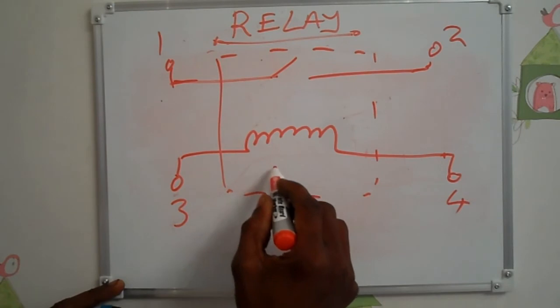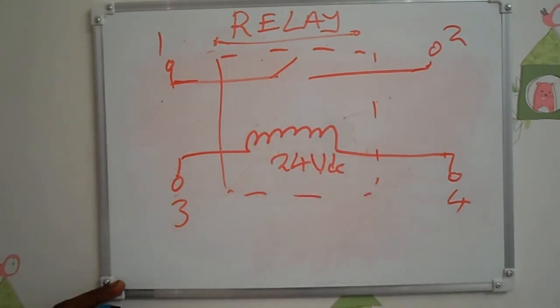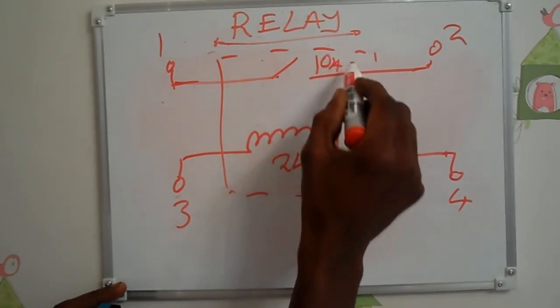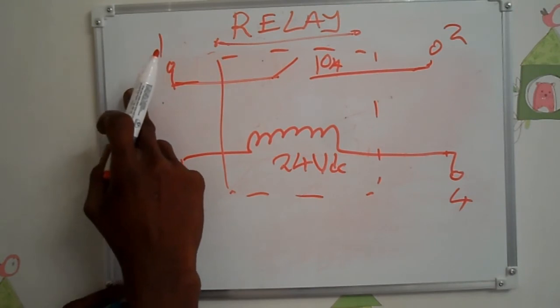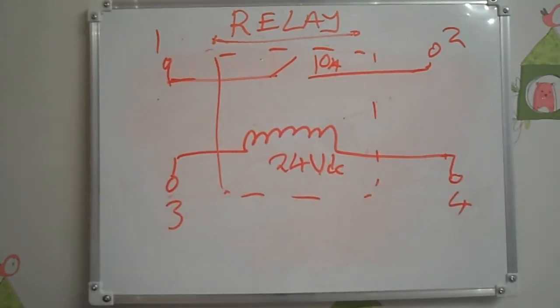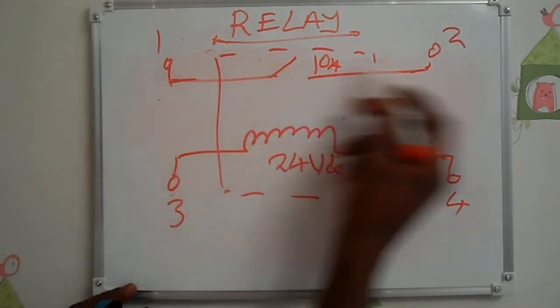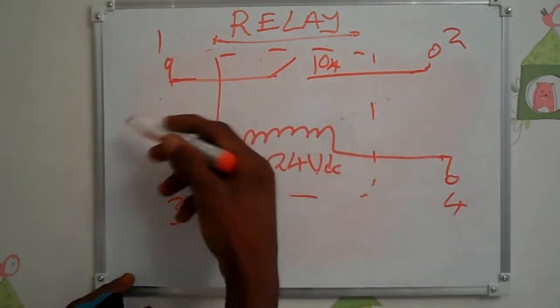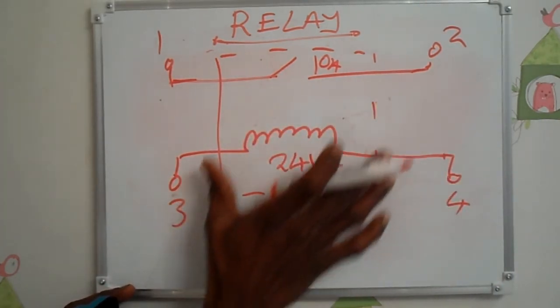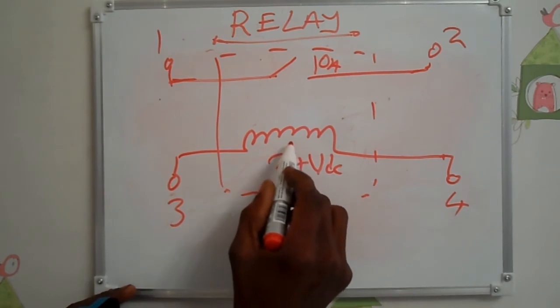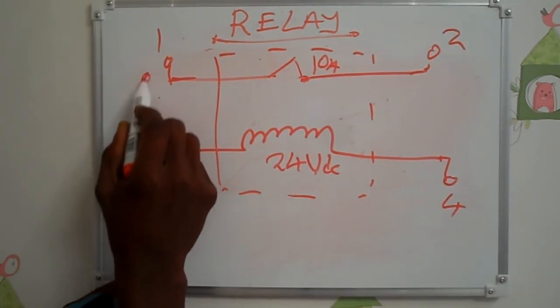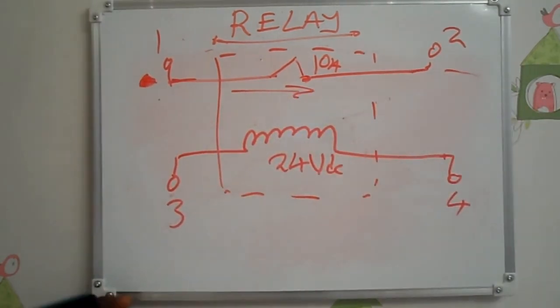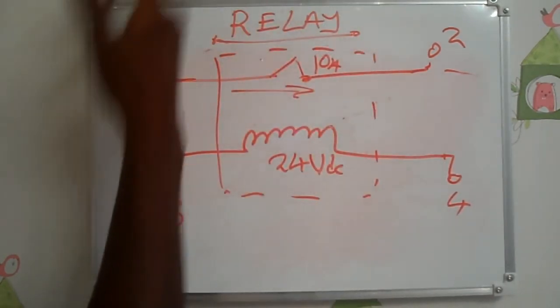The coil can be 24 volts DC and the contact can be 10 amps AC. You can energize the coil with DC voltage while AC current passes through the contact. This DC coil has nothing to do with the contact side. When the coil is energized, it drags the contact to close. Then whatever signal or message you have on the contact side can now pass to the other side. The coil can also be AC — 230 volts AC applied to the coil — while the message passing through the contact can be a DC signal or just a continuity.